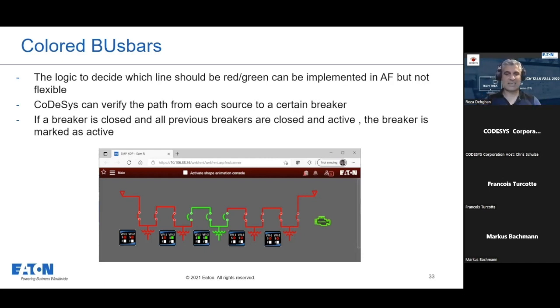So that's the way, basically we generate a list of points or an is-energized attribute for each section of the single-line diagram. Could be a breaker, it could be a section. No, sorry, it's not for a section, it's only for the breakers.